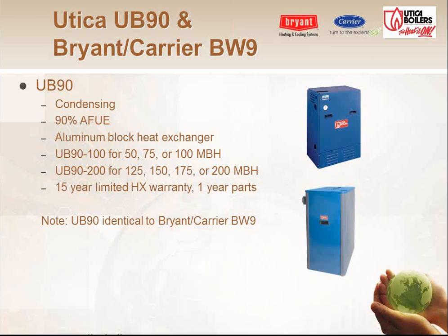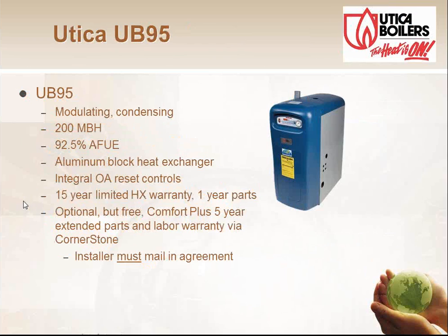These particular ones are only 90% AFUE, and they're just on-off. They do not modulate. But there are other ones that do modulate, which would be this guy here, the UB95, which is their big brother. They'll have full modulation, 90 to 93% efficient. The only bad thing about him is he only comes in one size, 200,000 BTUs. So we can only use it on certain jobs because of that.